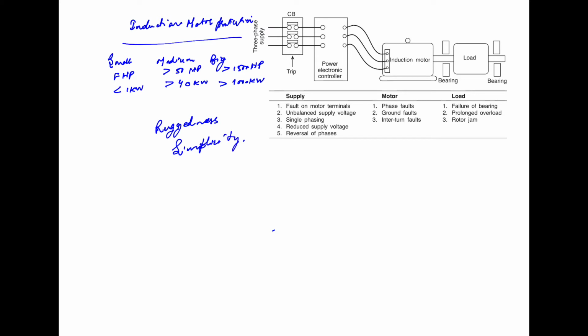Now, however, with the introduction of power electronic controllers, speed and torque control of the induction motor is now comparable with that of the DC motor. That's why nowadays we are using the induction motor everywhere. It comes in a wide range of ratings, from fractional horsepower motors used in tools and domestic appliances to motors of megawatt rating used for boiler feed pumps in thermal power stations.